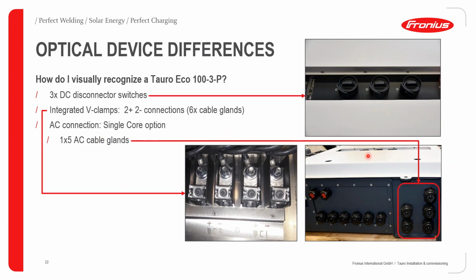Then on the AC side, you can see that we have only 5 cable glands provided. This means, therefore, that this inverter will not be capable of AC daisy chaining, as already explained before.